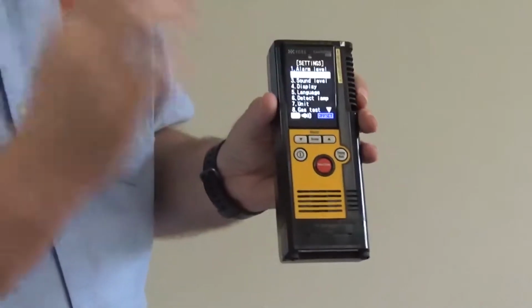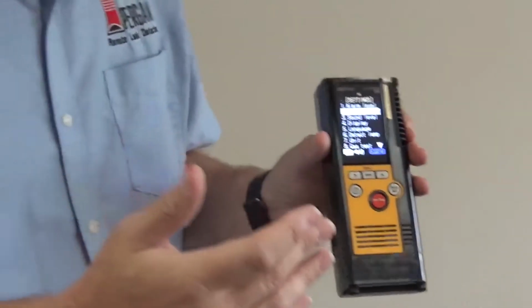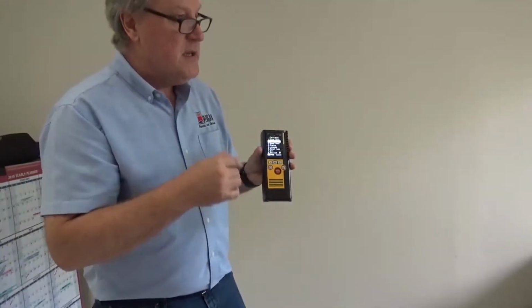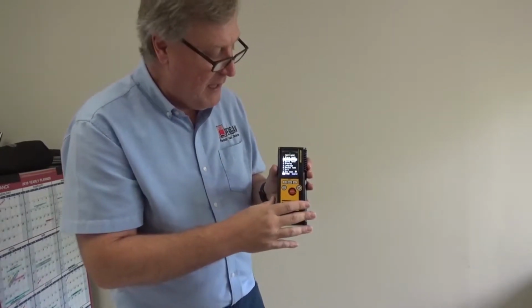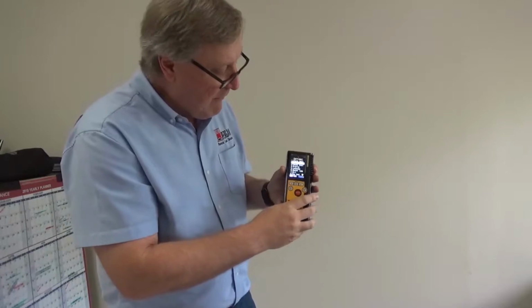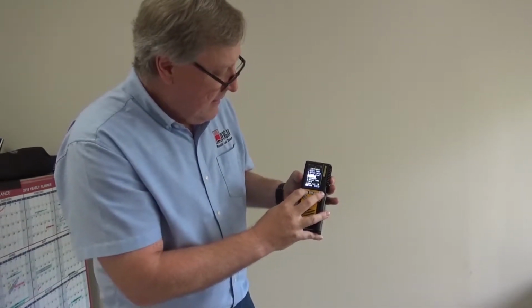Also, the offset can never be set at 0. My recommendation is that from a demo standpoint and maybe from an application start standpoint, put the offset at 5 and put the ppm times meter level at 25, and from there on you can adjust it up or down subject to your application.